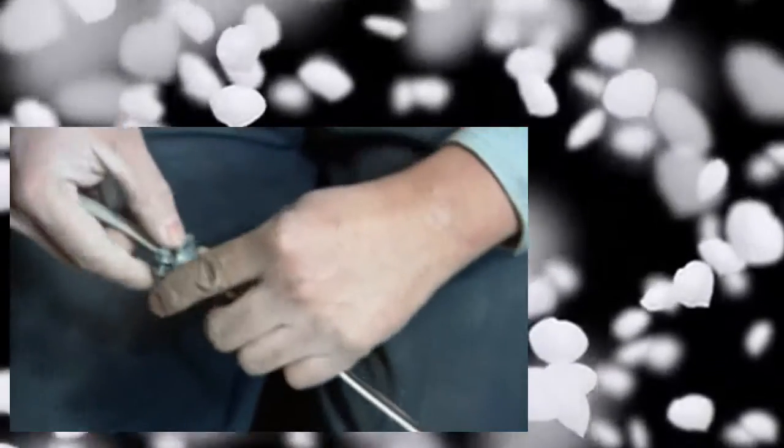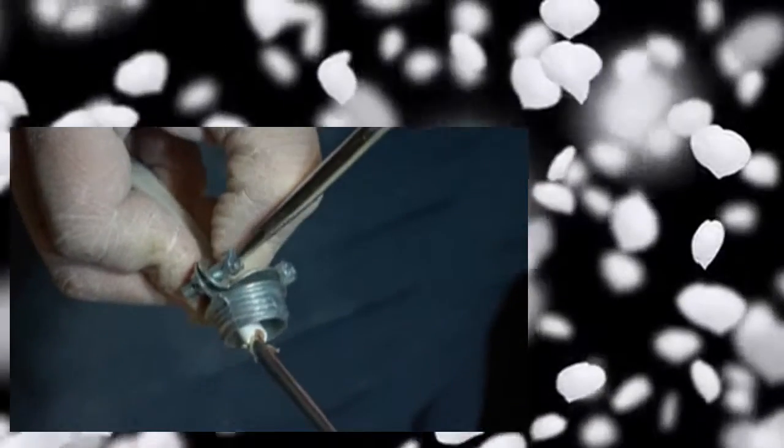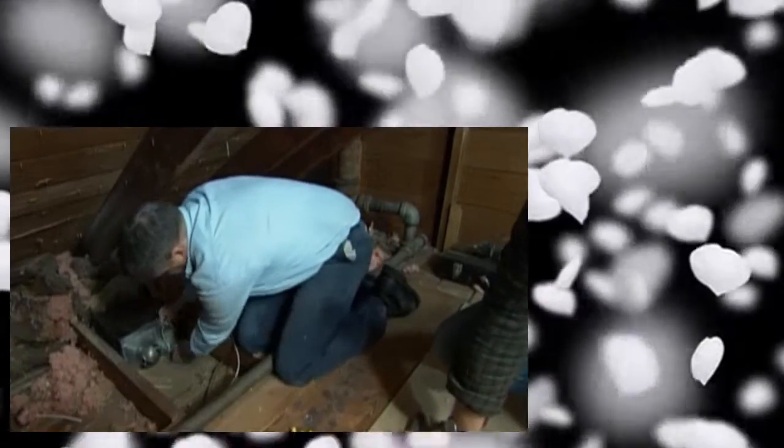Up here in the attic, we have the Romex we ran earlier from our switch. We're going to put the Romex connector on, pinch it down and just screw it in place. It's important that you make sure you use the clamp to hold the Romex in place rather than just putting the wire in the junction box. We don't ever want that connection to come undone.